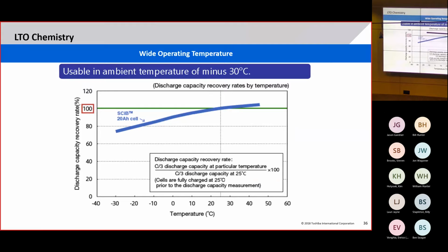This is a positive side effect, not necessarily a benefit for the data center, because I don't see anybody saying they want to run their data center at 10C or 0C. But it is positive in the sense that it's elastic with temperature. If you use the LTO batteries at a lower temperature than 25C, you're going to lose capacity while the environment is at that temperature. Once your temperature comes up, you regain that capacity, whereas with the other two chemistries, you lose the capacity permanently.